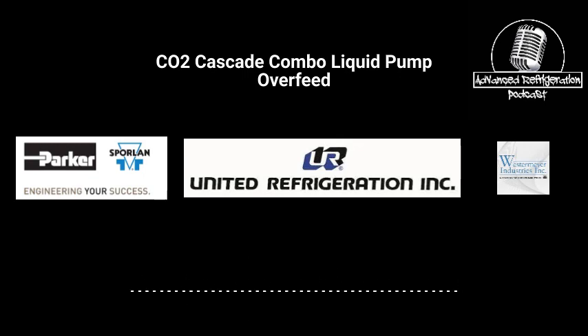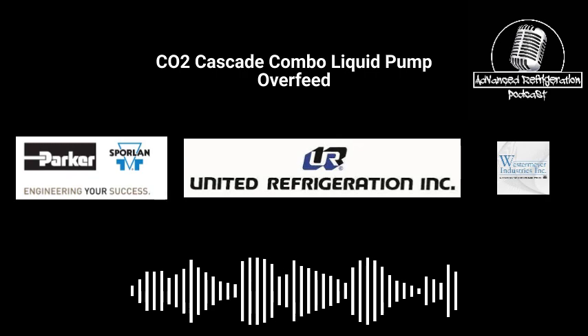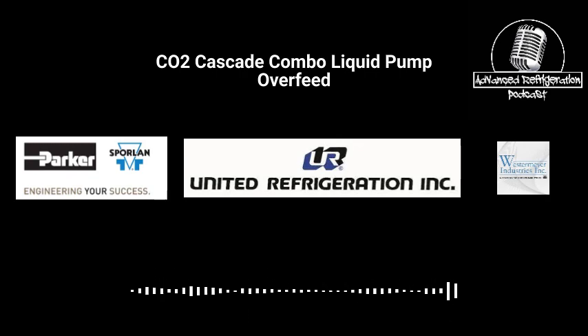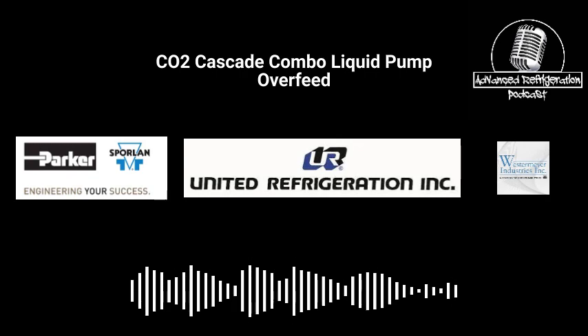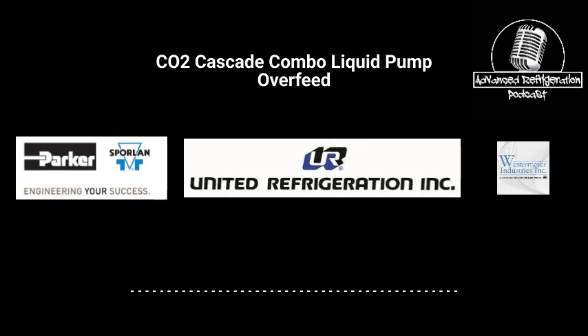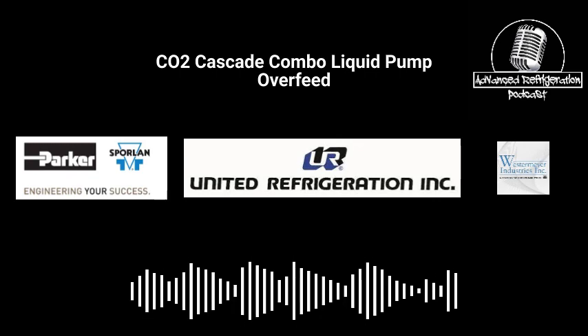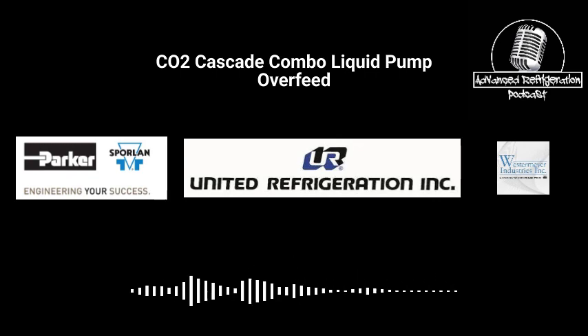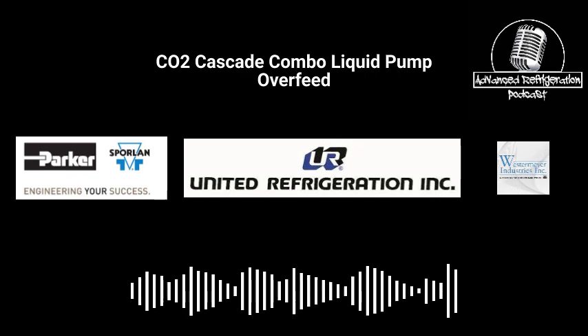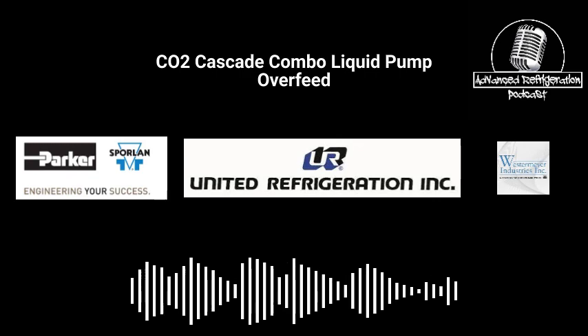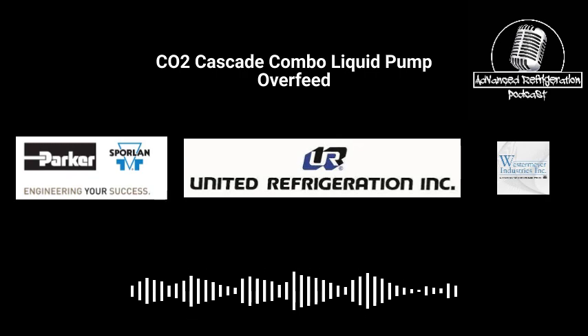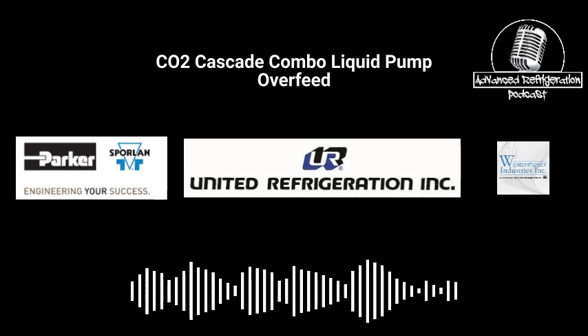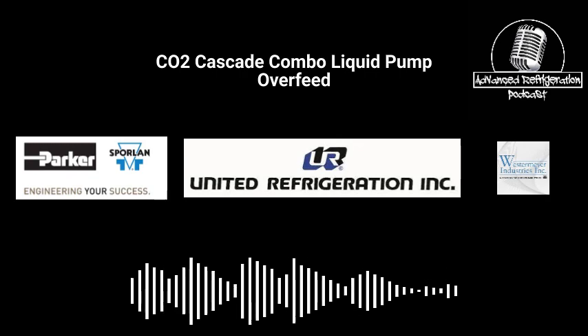But for the most part, unless you run them dry, that's the other reason why they have a differential setting on there: if it doesn't maintain more than like a 10-pound differential from the vessel pressure to the pump discharge. Because the pump discharge is going to probably bump that pressure up about 35 pounds or so, depending on the load, depending on how many cases are in defrost or whatever.